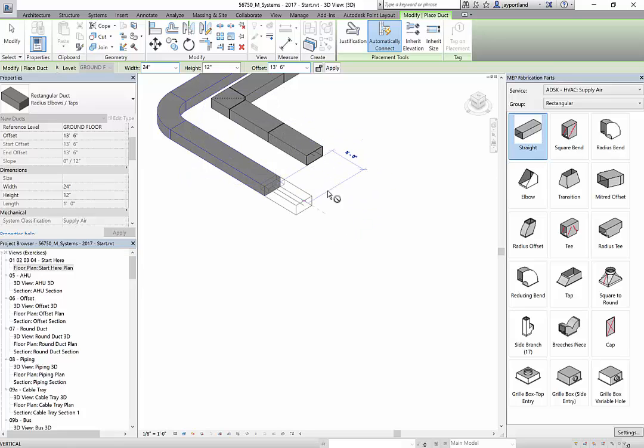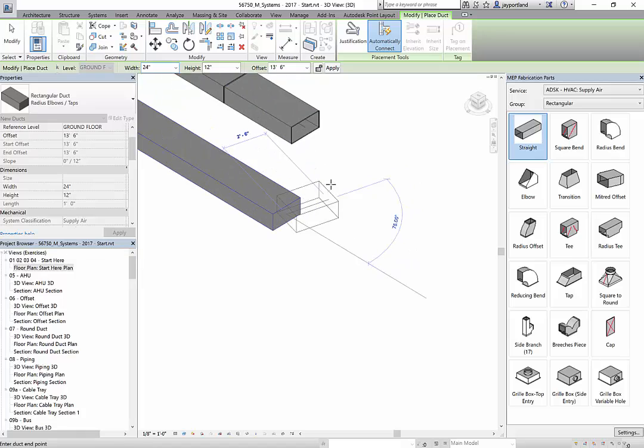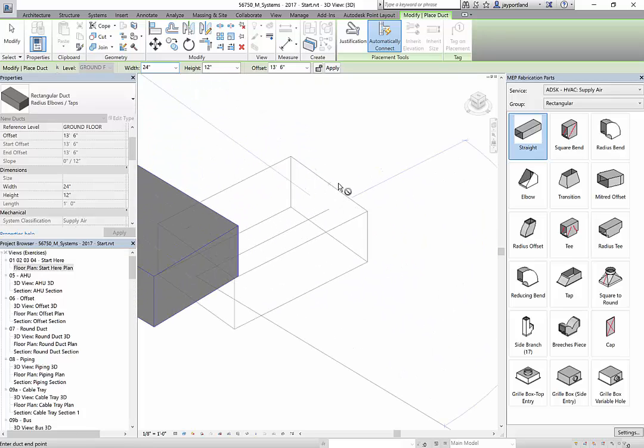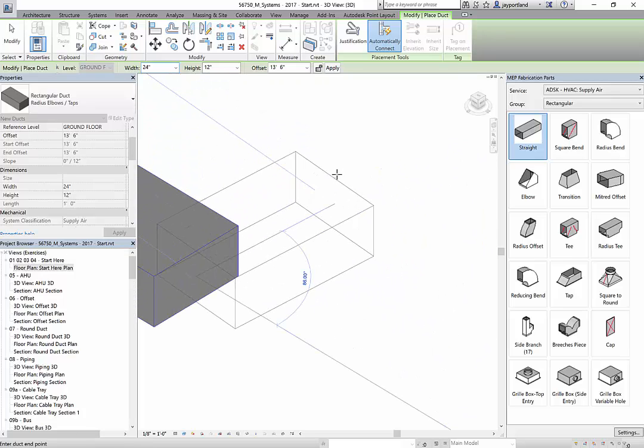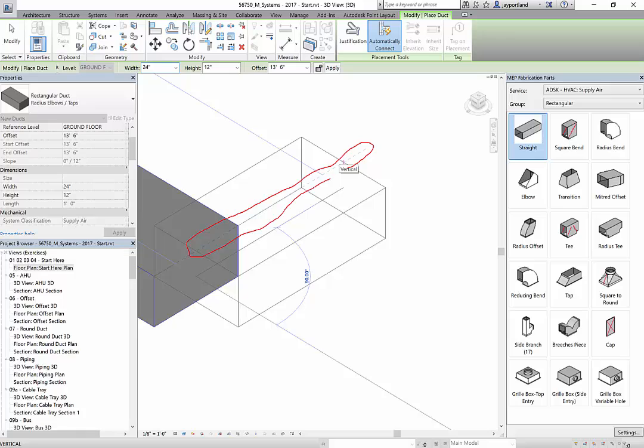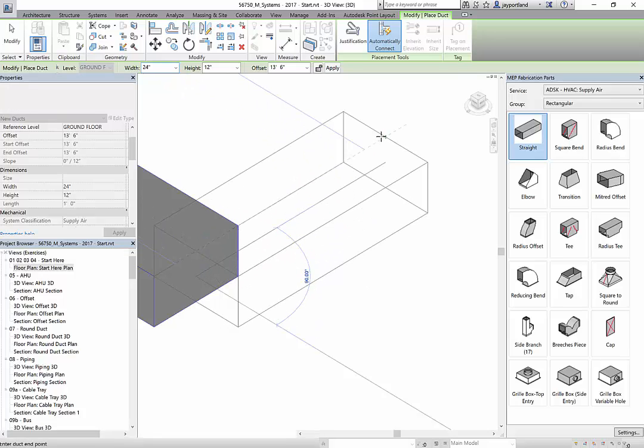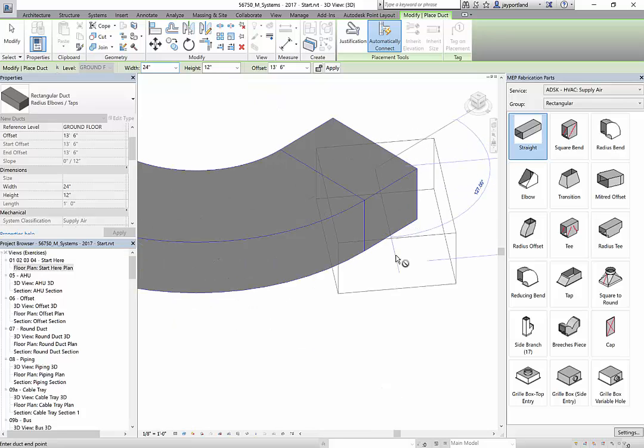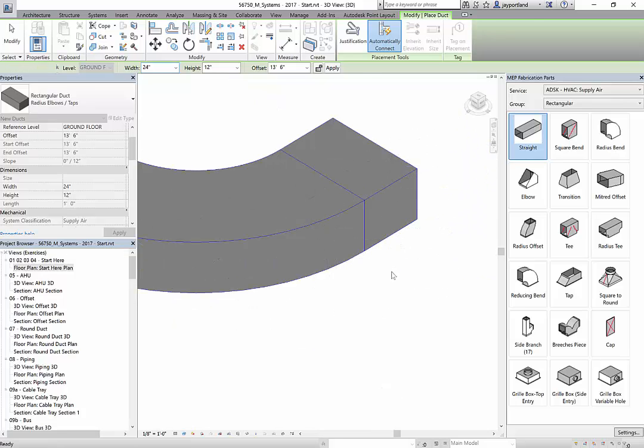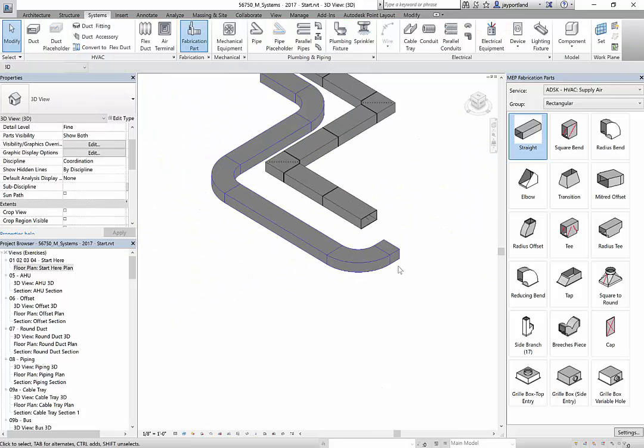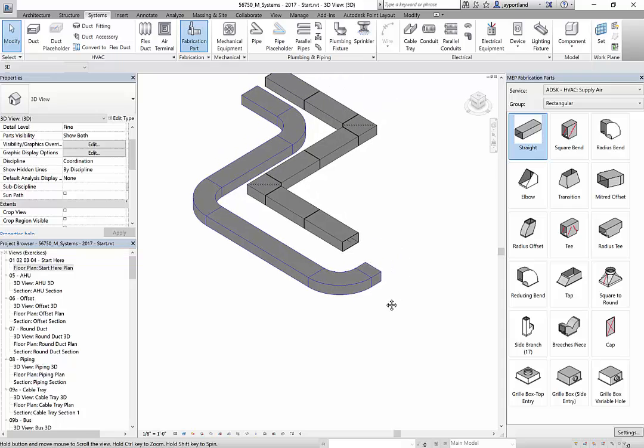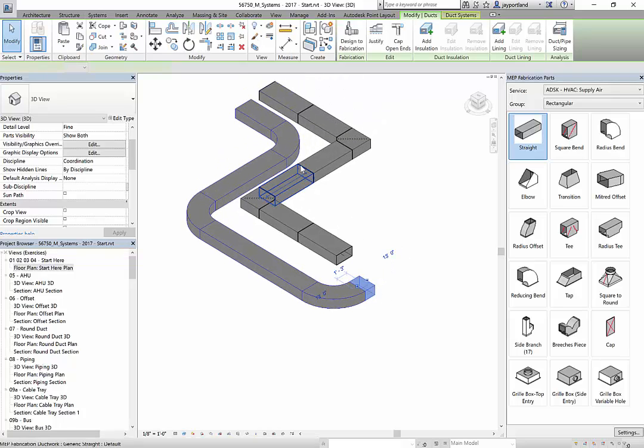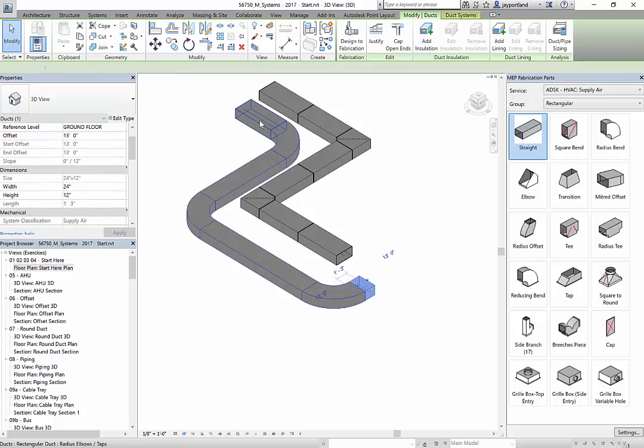So as I draw more ductwork, you'll see that it is, in fact, pulling along the top here. It's kind of hard to see. But you'll see the witness lines here pulling along the top center, the top middle of that duct. So if you absolutely have to draw ductwork justified at the top, the suggestion that I'm going to give you is use the classic Revit ductwork and then choose that run.